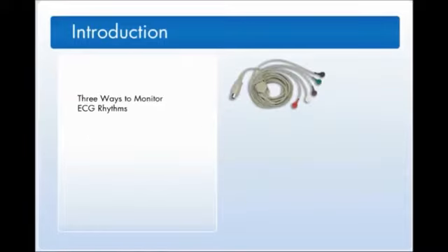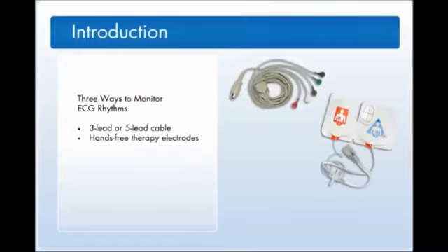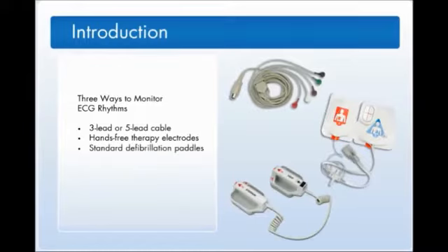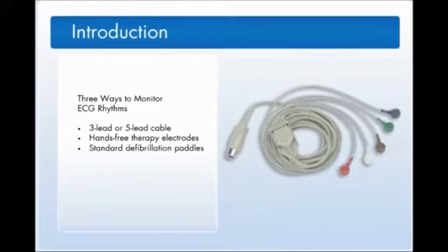You can monitor a patient's ECG by using a 3-lead or 5-lead ECG patient cable, hands-free therapy electrodes, or standard defibrillation paddles. In this module, we will focus on using a separate 3-lead or 5-lead ECG patient cable. To learn more about how to prepare the patient's skin and how to place ECG electrodes on a patient, review the Prepare Patient module. It is important to remember that once you have prepared the patient's skin, snap the lead wires onto the electrodes before applying them to the patient.